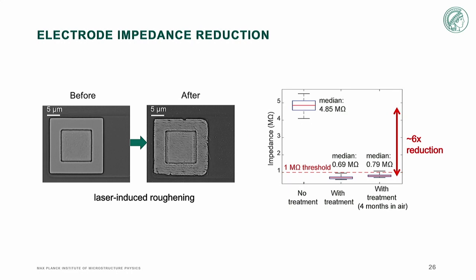One trick we used: as fabricated, the electrodes from AMF look like that, but the impedance was quite high, around 5 megohm, and with such high impedance you cannot get good quality recording. So the impedance has to be less than about 1 megohm.